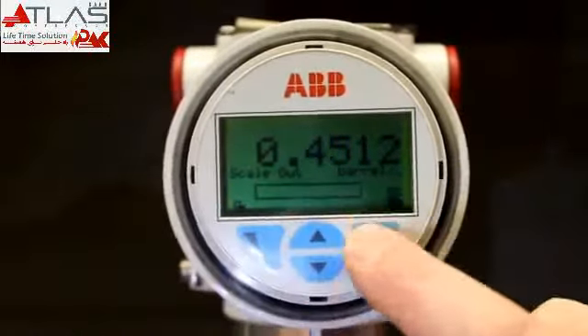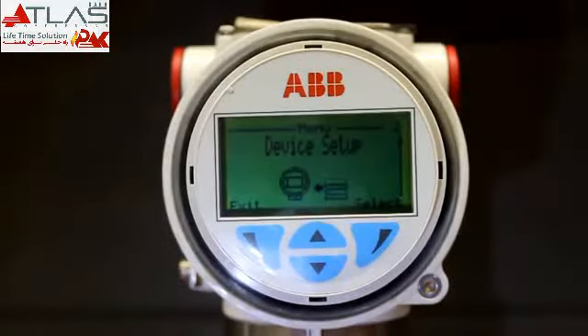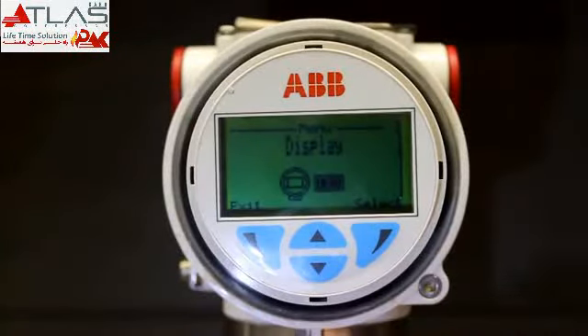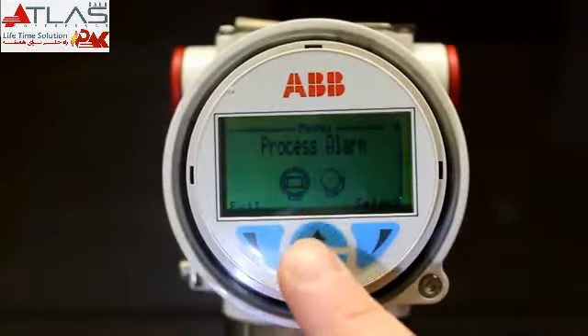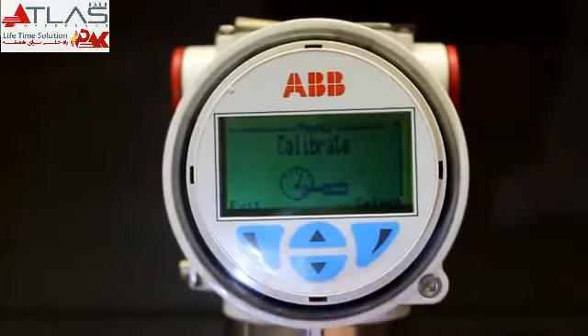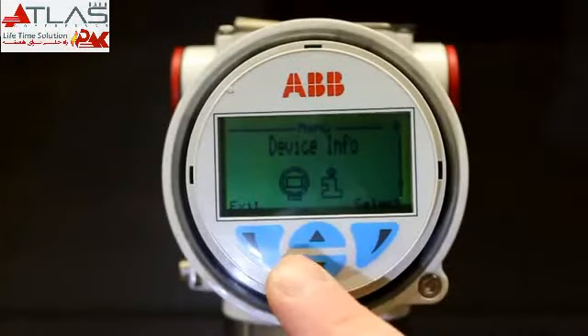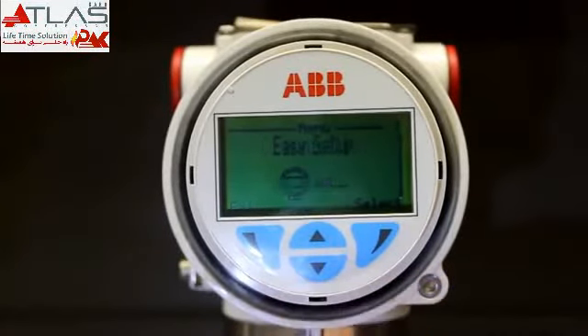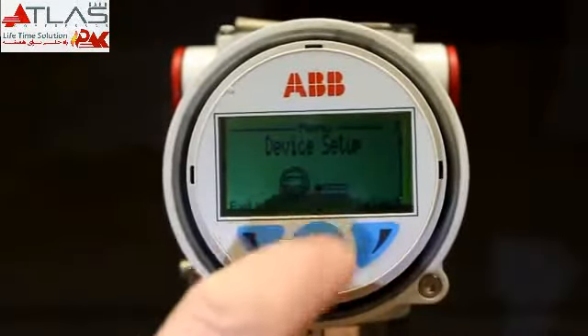To start, we're going to hit the two center buttons at the same time, and after a few seconds you'll have an icon come up on the right or left side, and you can get into the menu. Once you're in the menu, you use the left or right buttons: in this case, exit on the left and select on the right. The up and down arrows in the center will scroll you through the menu options. If we go down, you hit display, process alarm, calibrate, totalizer, diagnostics, device info, communication, easy setup, and then back to device setup.